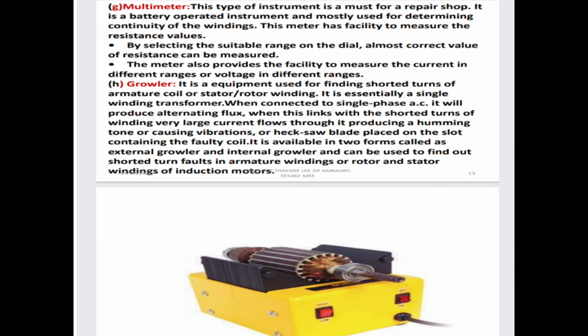So the next is the multimeter. What is a multimeter? This type of instrument is a must for a repair shop. It is a battery operated instrument and mostly used for determining continuity of the windings. This meter has the facility to measure the resistance value. By selecting a suitable range on the dial, almost correct value of resistance can be measured. The meter also provides the facility to measure current or voltage in different ranges. So the multimeter is used to measure different ranges of current and voltage.